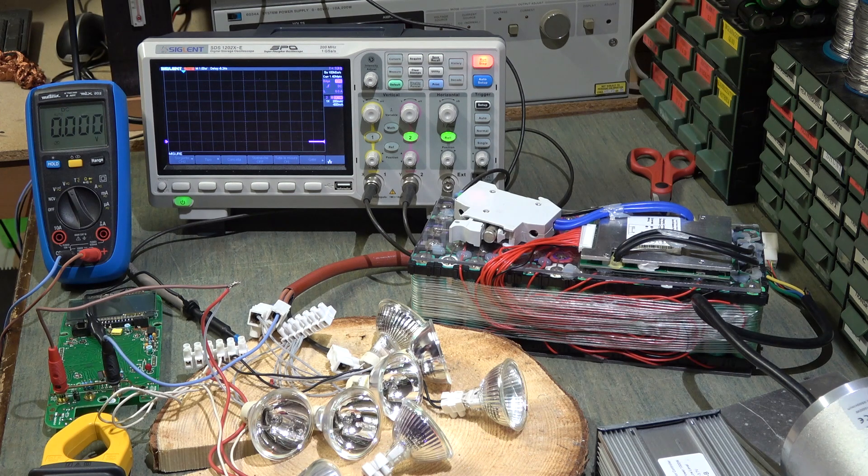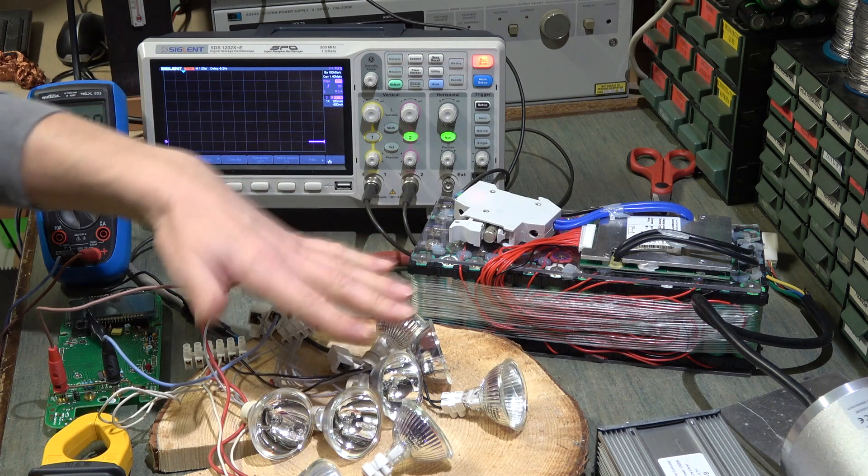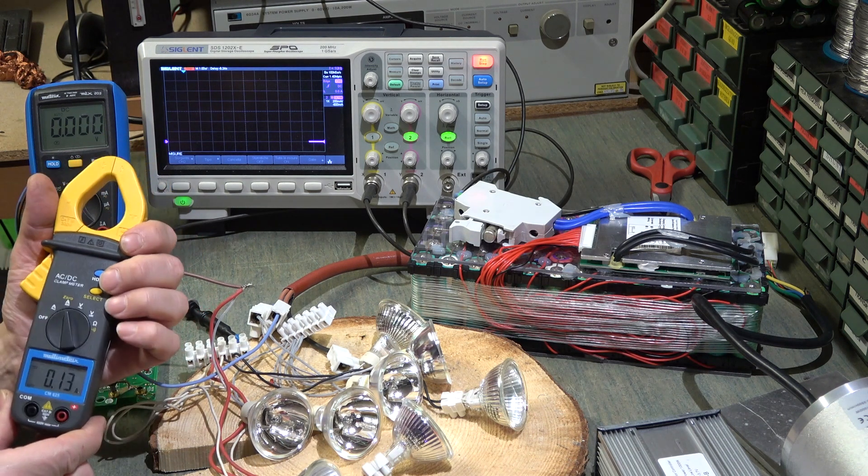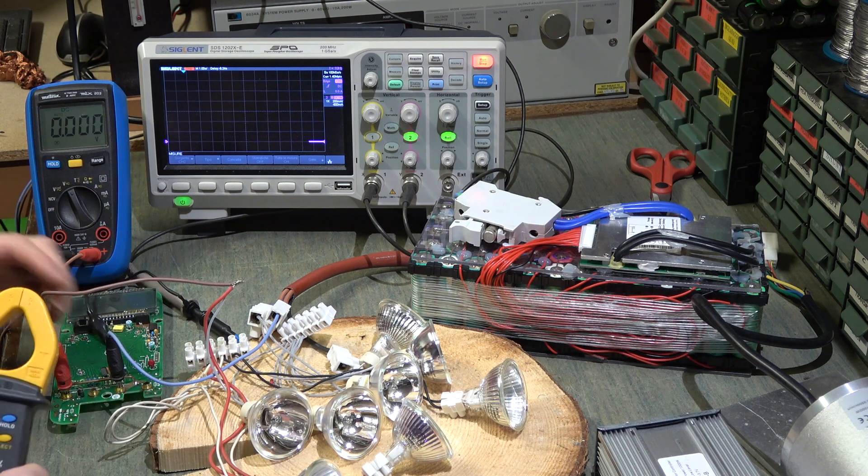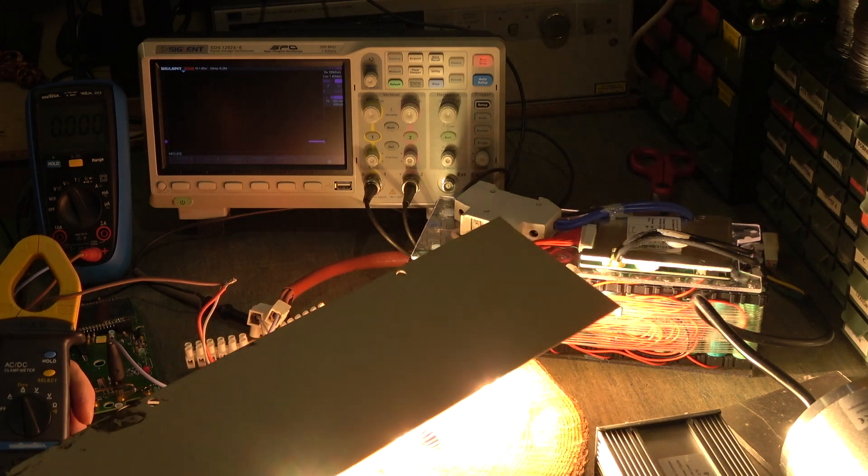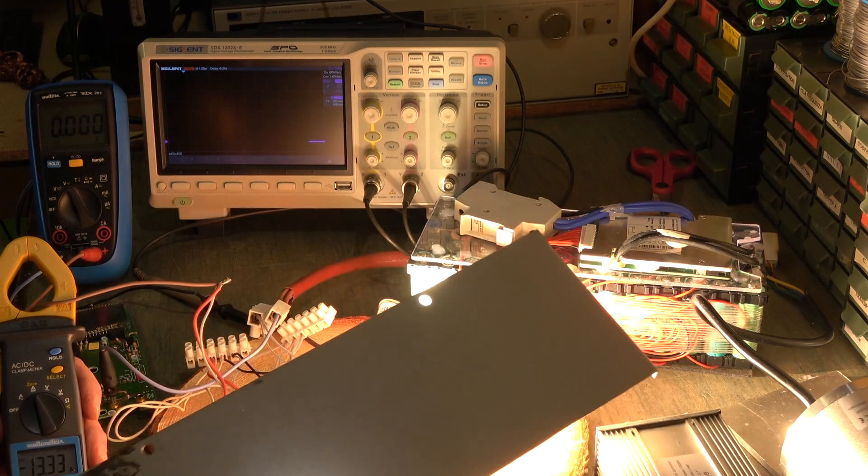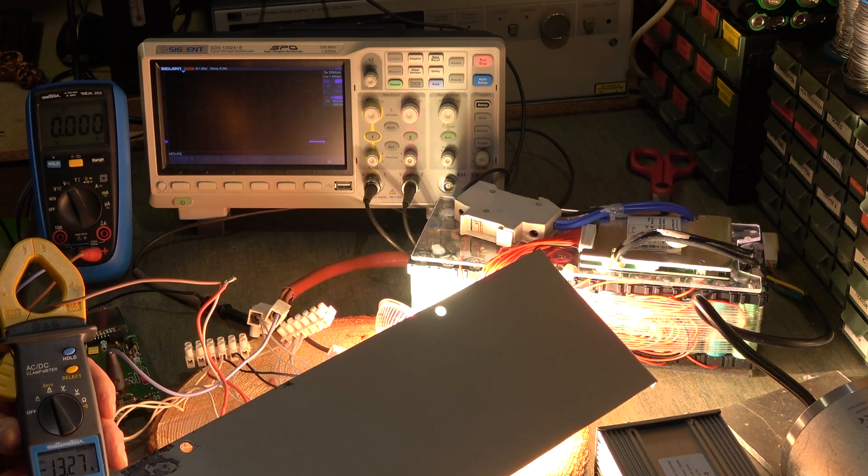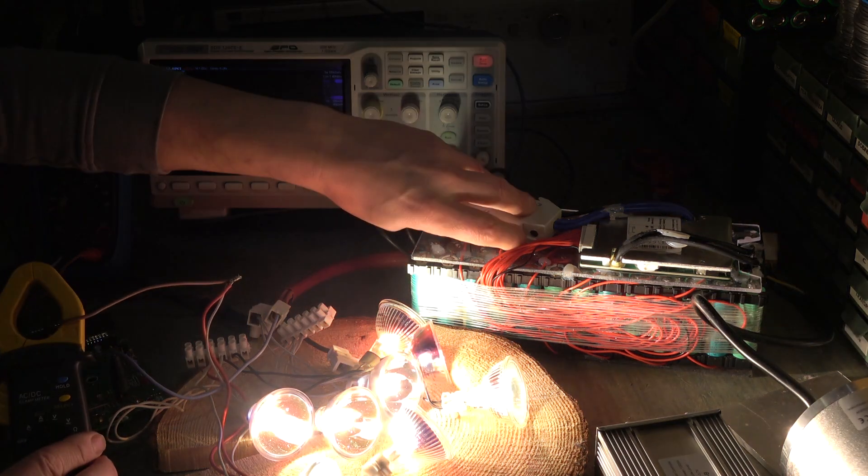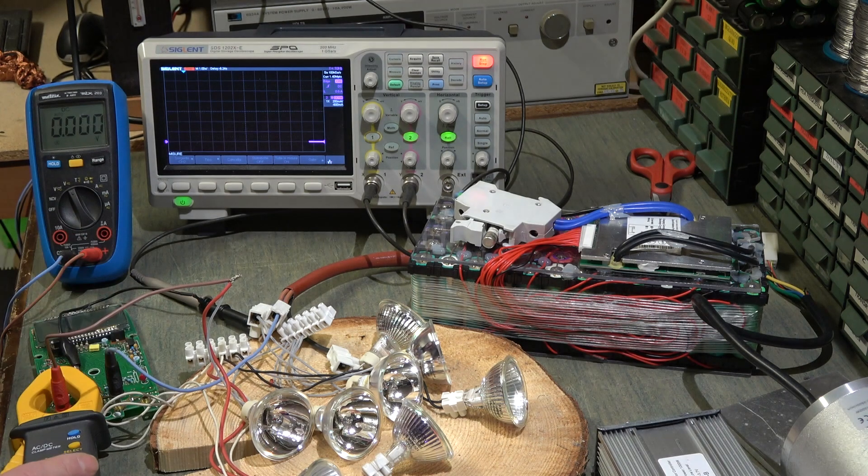Faremo anche un calcolo per vedere quanti watt abbiamo a questa batteria. Allora adesso andrò a fare un'accensione, metto il tester in ampere, la pinza amperometrica faccio la zero, la metto qua su un ramo e vado ad accendere. Vediamo che assorbe 13 ampere e 70. Vogliamo coprire un po' la luce perché vediamo che siamo a 13 ampere e 30, adesso si abbassa perché logicamente con quel carico qua sta assorbendo molta corrente.